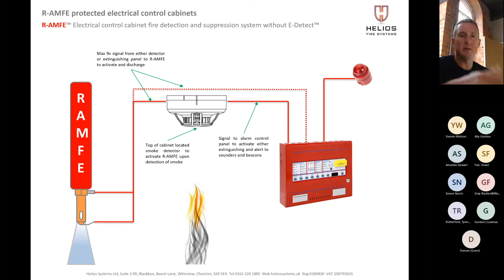To give you a rough idea on price, a one cabinet system would be, including the alarm panel and everything else, probably about £560. Whereas if you were looking at a FireTrace system or Reacton or any of these other systems that are out there, you're looking at about £1,500 or more per cabinet, and then you have to have multiples. With this, if you only got one cabinet, it's one at £500. If you've got multiples, that price comes down because you've already got your alarm panel, so your next one might be £400, and then it goes down, down, down from there.